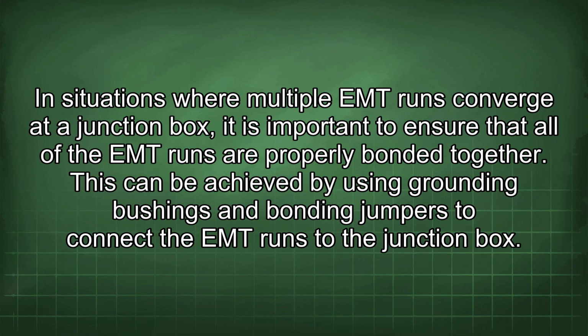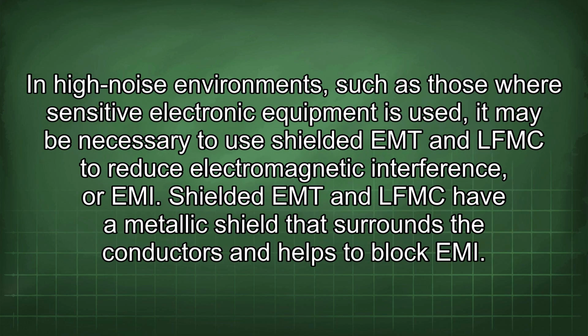In situations where multiple EMT runs converge at a junction box, it is important to ensure that all of the EMT runs are properly bonded together. This can be achieved by using grounding bushings and bonding jumpers to connect the EMT runs to the junction box. In high-noise environments, such as those where sensitive electronic equipment is used, it may be necessary to use shielded EMT and LFMC to reduce electromagnetic interference, or EMI. Shielded EMT and LFMC have a metallic shield that surrounds the conductors and helps to block EMI.